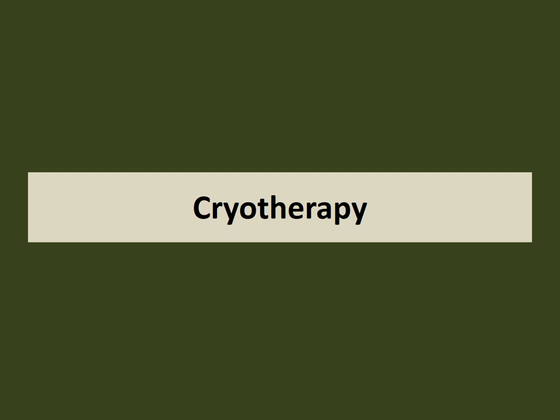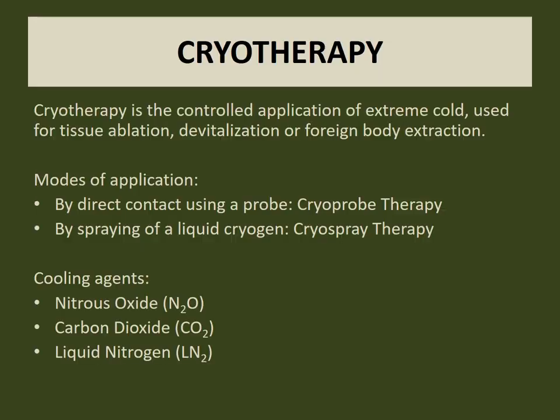Now that we understand how our equipment produces cold, let's discuss cryotherapy. It is defined as the controlled application of extreme cold, used for tissue ablation or devitalization. It is an easy-to-perform procedure with minimum complications. The mode of application can be by direct contact using a probe, or by spraying of a liquid cryogen. Available cooling agents are nitrous oxide, carbon dioxide, and liquid nitrogen. Nitrous oxide is stored in the liquid state at room temperature in a high-pressure bottle. Carbon dioxide has undergone technological advances over the years and is becoming the cryogen of choice for certain applications. We will discuss liquid nitrogen later during this video.